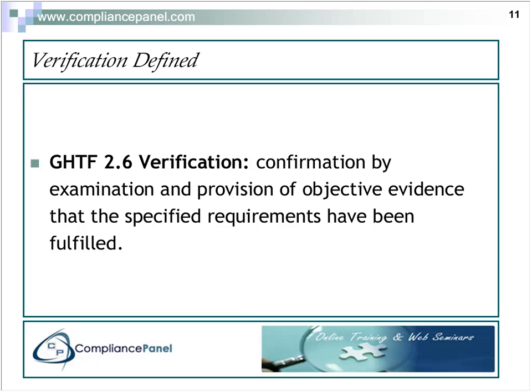We talked about that earlier. But verification is also an inspection activity that may take place during the production of our product, and that could be at incoming, in process, or final inspection. It's also a verification activity that may take place during our process validation. In other words, we're following this particular protocol, and we're verifying that that protocol was executed successfully. So we'll provide this objective evidence that this protocol has been actively and successfully completed.